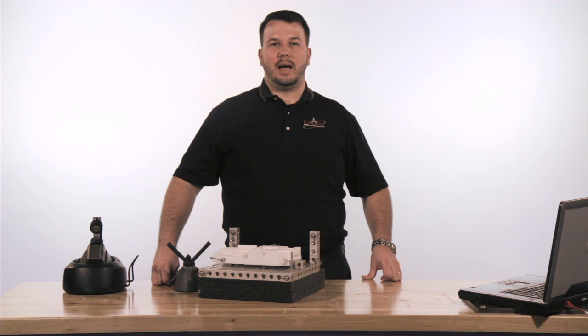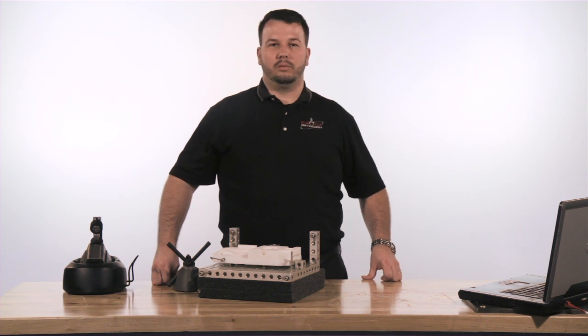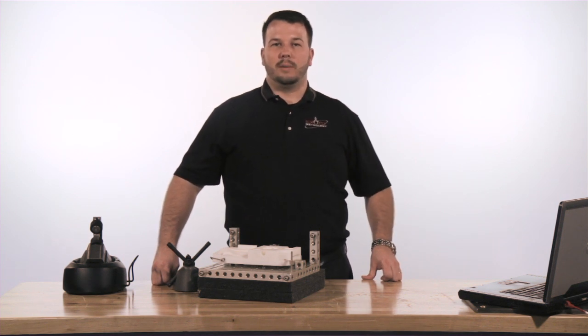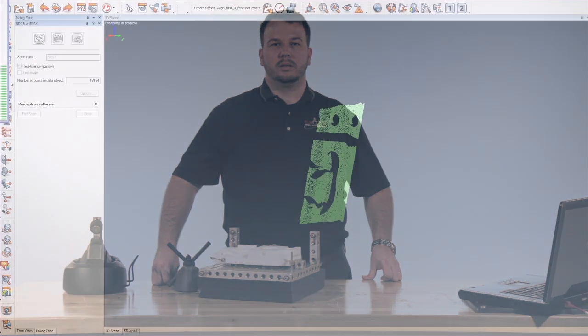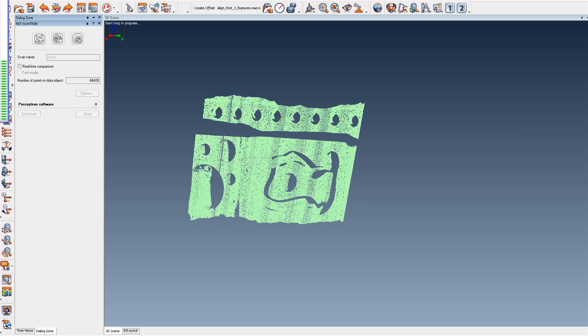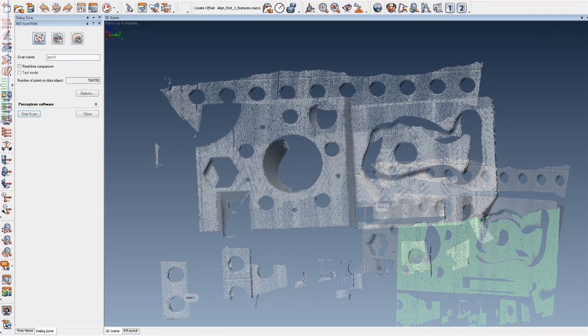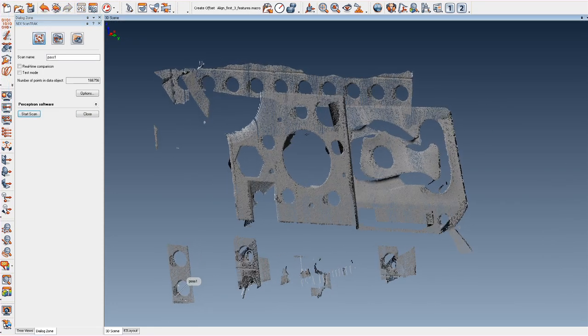Why choose the NDI Optotrak? Some of the major benefits include a solid-state tracker, meaning there are no moving parts. Various measurement volumes ranging from 3 cubic meters up to 20 cubic meters. There are wireless options for the probing and the LED targets. Its probes and scanner are lightweight and ergonomic. It also comes with a calibrated artifact that is used to perform in-house calibration of the system so it doesn't have to leave your facility.